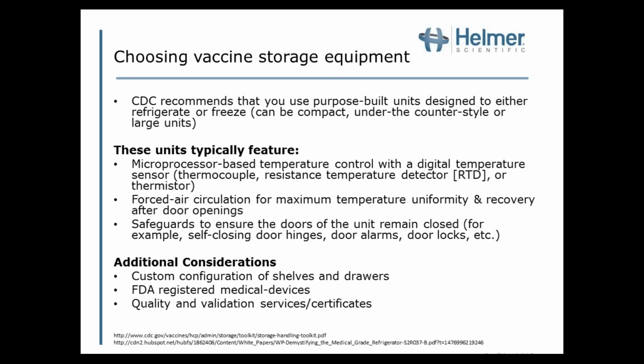Pharmaceutical-grade units usually have microprocessor-based temperature control. Instead of having to set a dial — like in a household unit that goes from 1 to 9, turning the knob trying to get it just right between the 4 and the 5 and hoping it'll stay in range — with these units you actually set the temperature, say 41 degrees Fahrenheit, and it brings it within that range, taking the guesswork out of it.